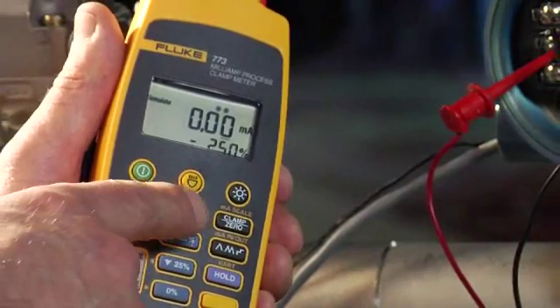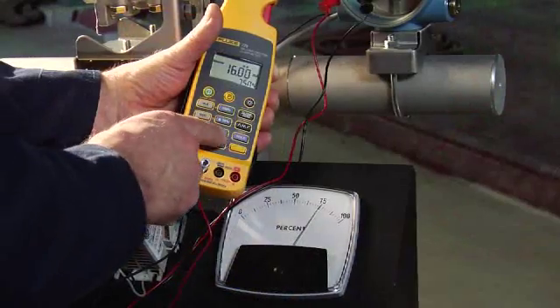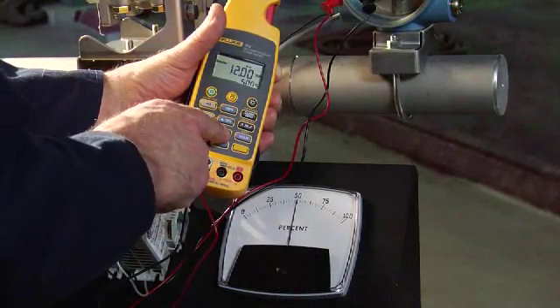Select milliamp simulate, then dial up the output and test the loop. The transmitter is in series with the milliamp signal as shown by the local indicator.